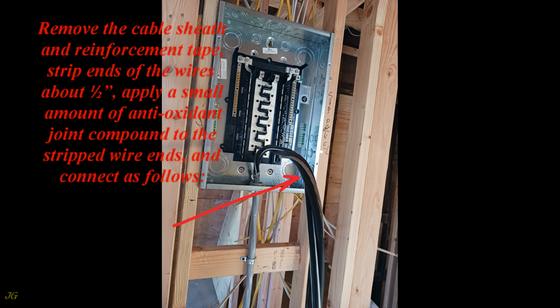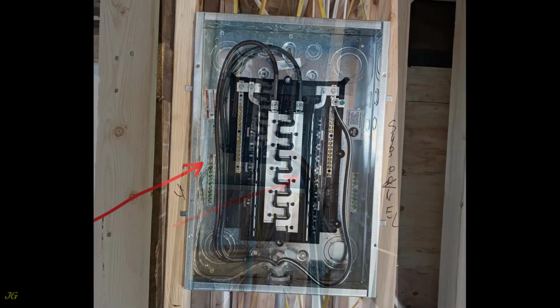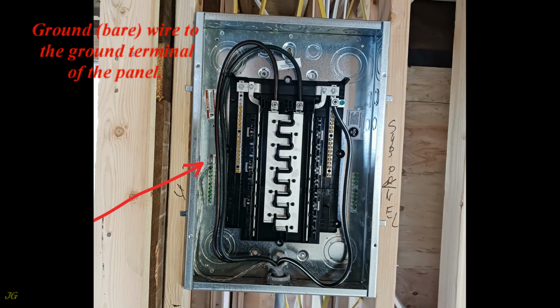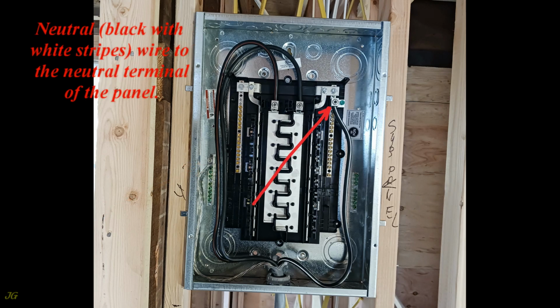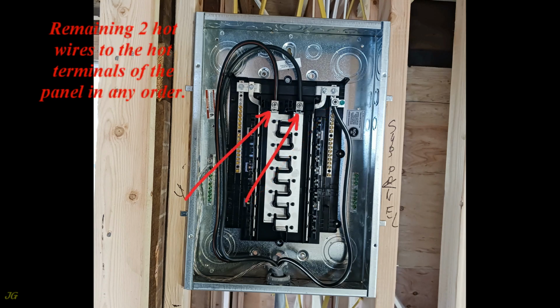Remove the cable sheath and reinforcement tape. Strip ends of the wires about 1/2 inch. Apply a small amount of antioxidant joint compound to the stripped wire ends, and connect as follows. Ground, bare wire to the ground terminal of the panel. Neutral, black with white stripes, wire to the neutral terminal of the panel. Remaining 2 hot wires to the hot terminals of the panel in any order.